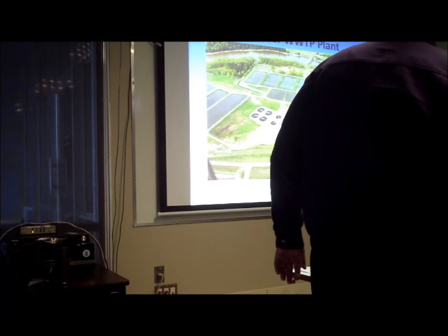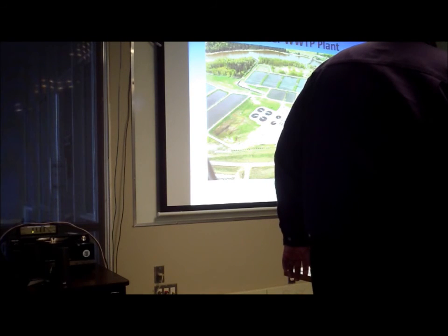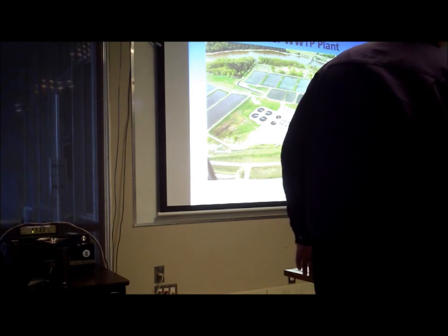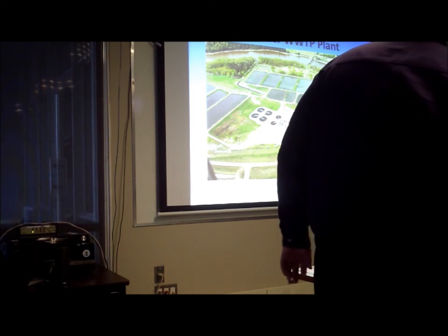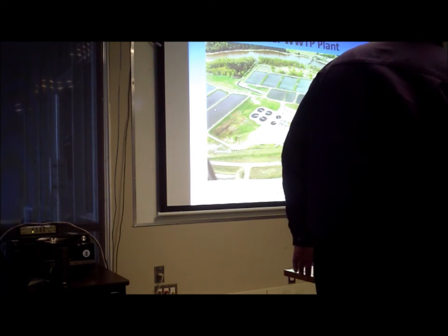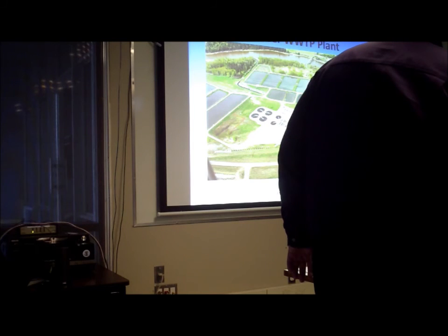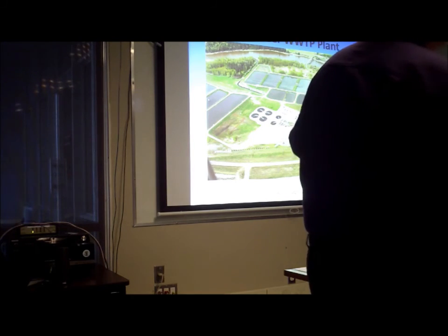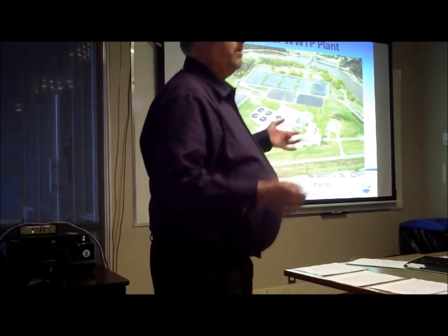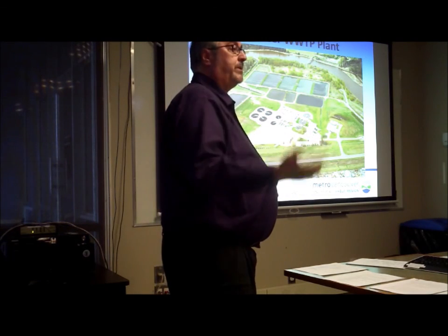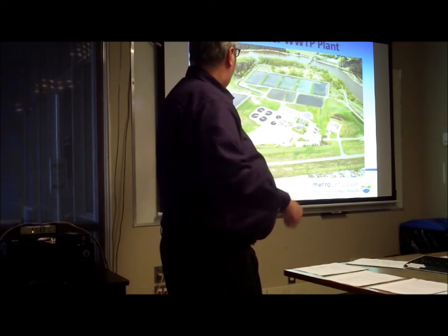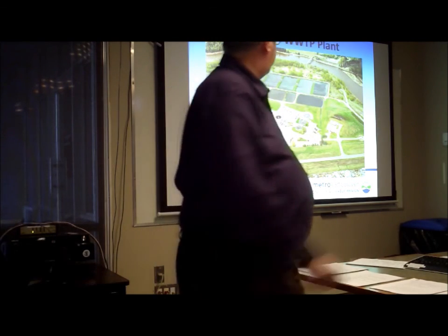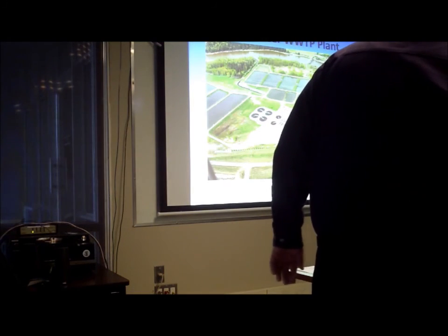And this building here housed the DAF units, the dissolved air flotation, which took the place of these gravity thickeners. And like Iona, Red Deer had digested sludge lagoons. And this here, I believe, was our supernatant cell. So once the sludge settled out, we would siphon into a supernatant cell and then pump that back to the headworks of the plant, typically at low flows.